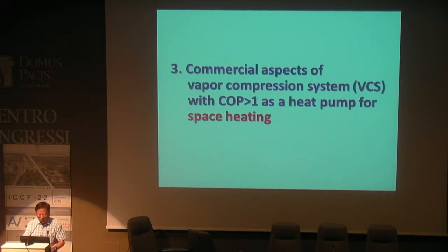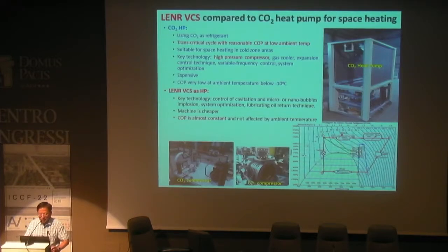If we use that as a heat pump for space heating, not water making, then I compare with a CO2 heat pump I developed several years ago with a company. The CO2 heat pump has been produced in large numbers in Japan. It's a commercial product. It's a kind of transcritical cycle with reasonable COP at low ambient temperature. But because of the CO2, it runs at a transcritical cycle, so with high pressure. The pressure inside the system is higher than 100 bar. So the machine is expensive and has very low COP at temperatures below minus 10 degrees.